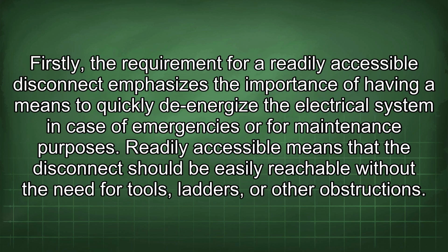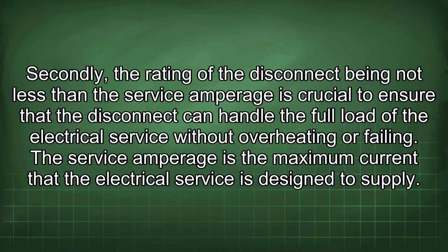Firstly, the requirement for a readily accessible disconnect emphasizes the importance of having a means to quickly de-energize the electrical system in case of emergencies or for maintenance purposes. Readily accessible means that the disconnect should be easily reachable without the need for tools, ladders, or other obstructions. Secondly, the rating of the disconnect being not less than the service amperage is crucial to ensure that the disconnect can handle the full load of the electrical service without overheating or failing. The service amperage is the maximum current that the electrical service is designed to supply.